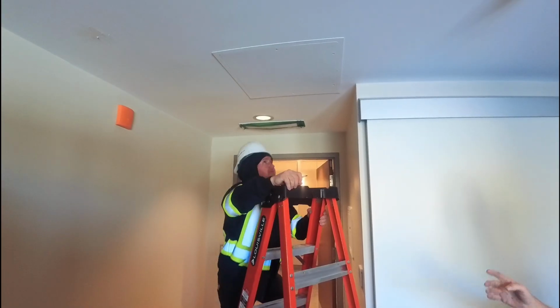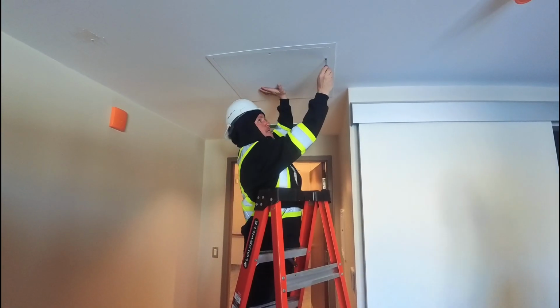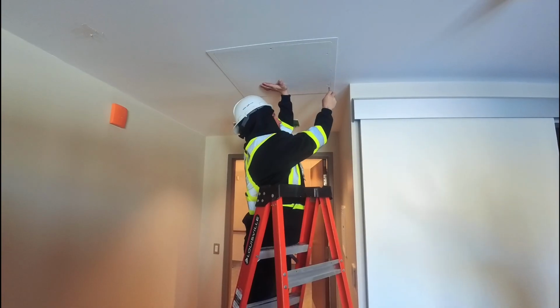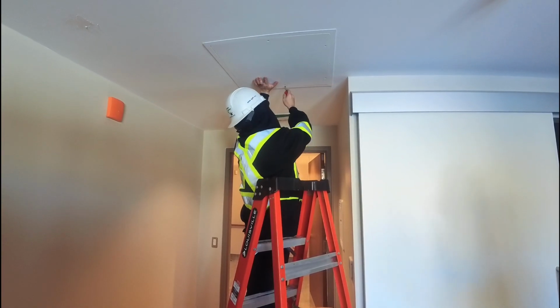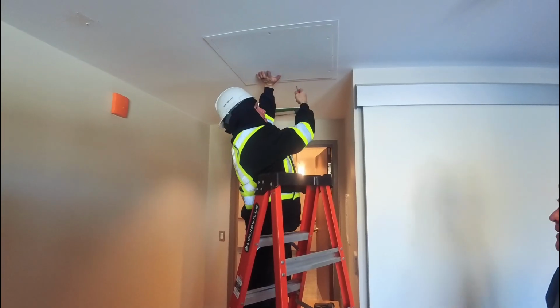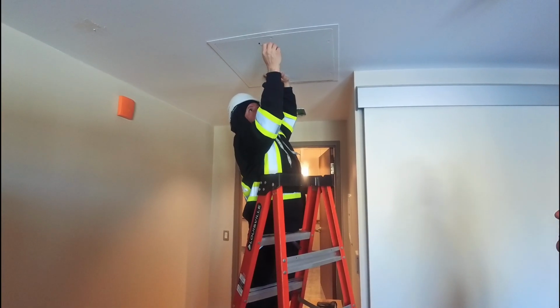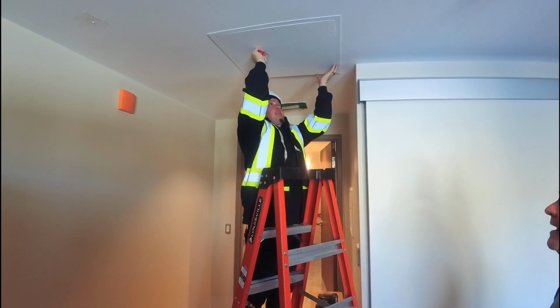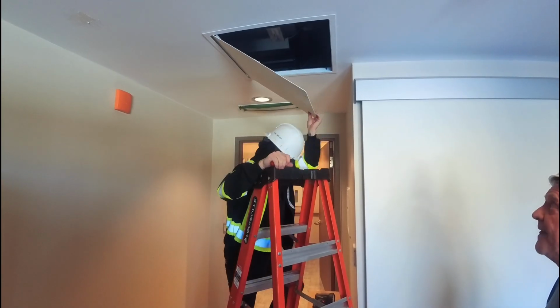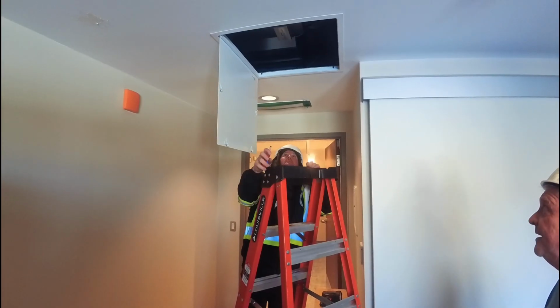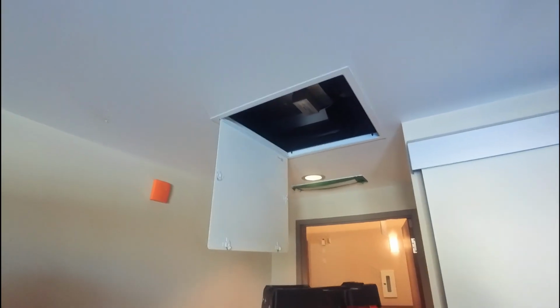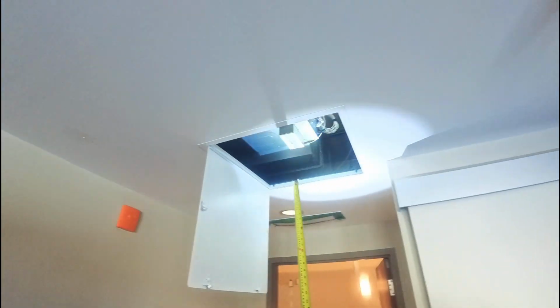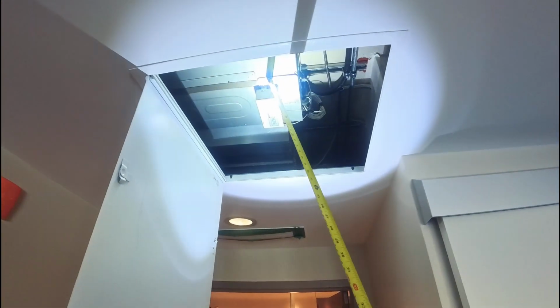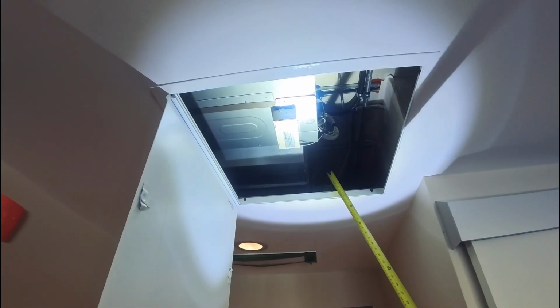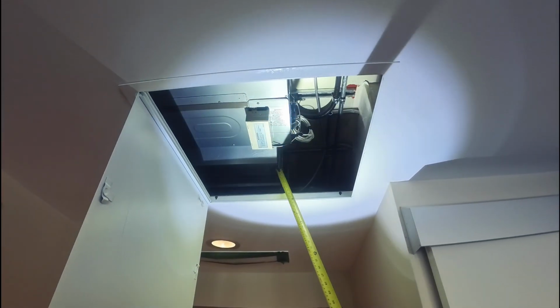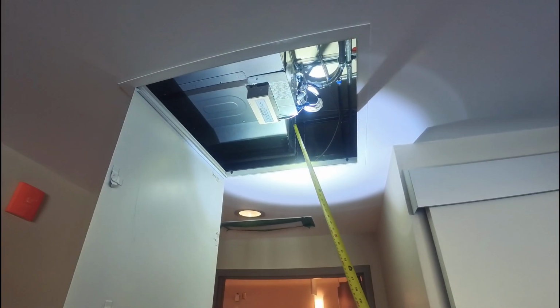We opened one last week, Jay and I, and we went through the filter change, and of course the duct heater that's associated with this as well, right? All right. There we go. So up above each access door in the suite at this location is a fan coil unit. On the return side of the fan coil unit, you'll see a small door. That's where the filter goes in.